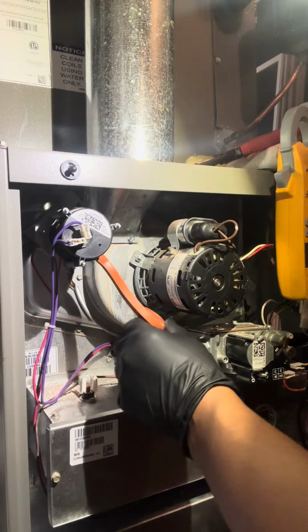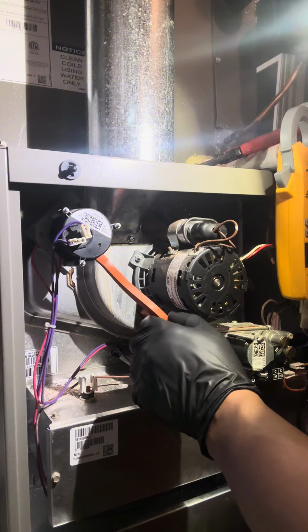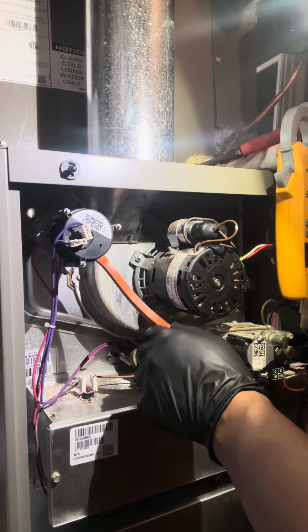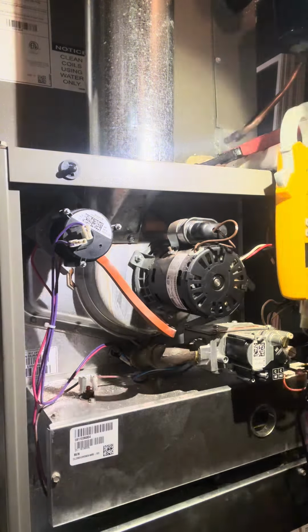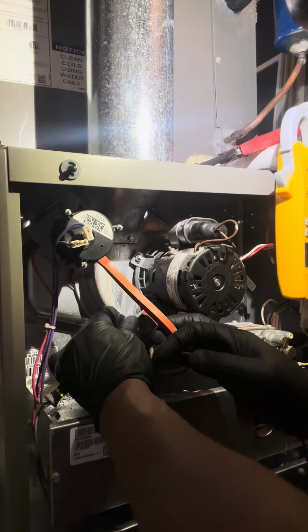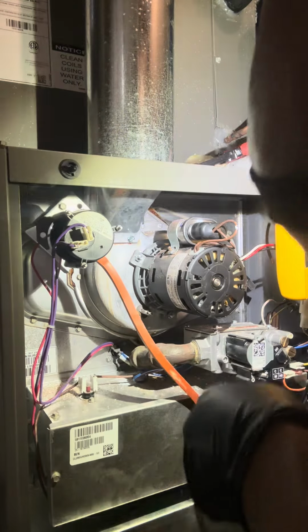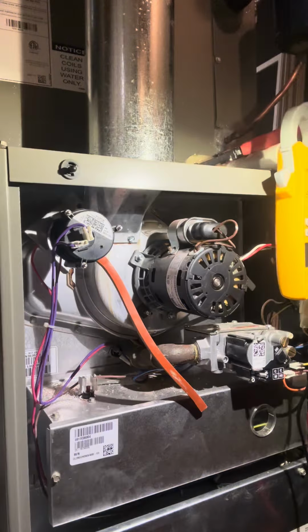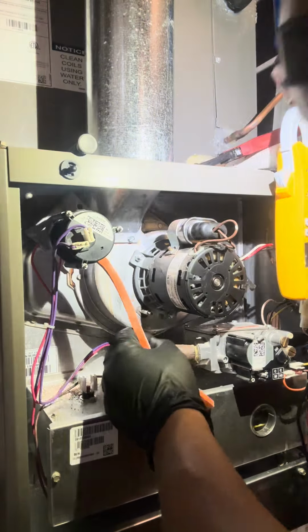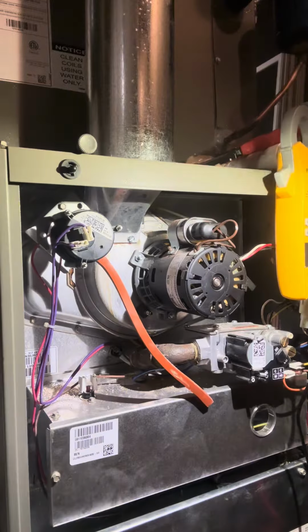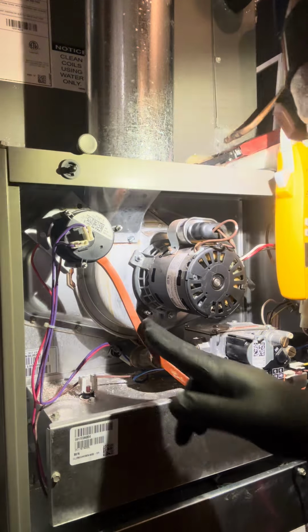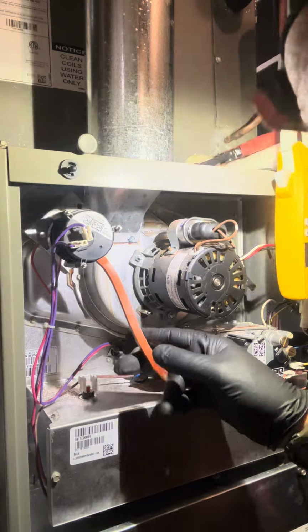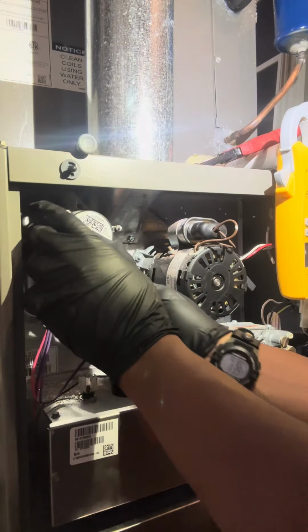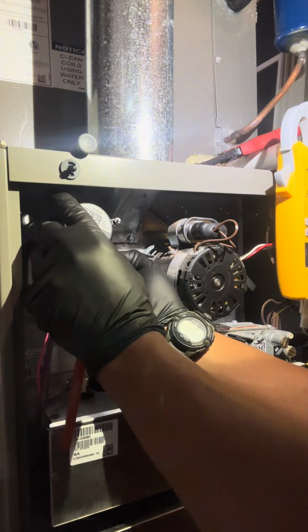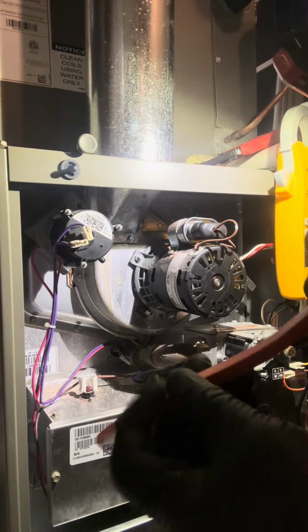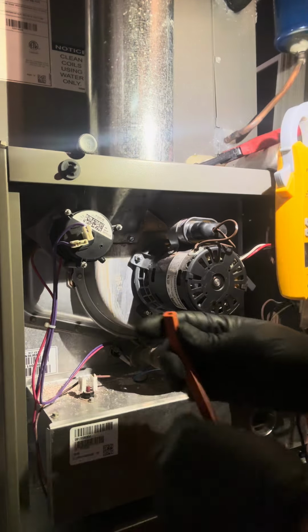home. So what we're going to do is we're going to pull off this tube, and we're going to make sure that it's clear, it's not clogged, and there's no debris in it that can, for some reason, be setting off this pressure switch. All right, gonna get a look in there. Make sure that that port is clear. That is typically where you'll end up seeing a lot of failures on these units, is this port right here. It will get clogged with debris and dirt coming from the inducer and from your exhaust. So you can pull this off, go through it. That is good.